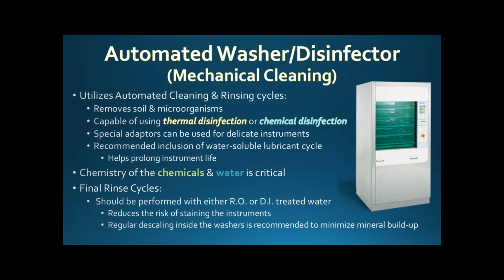Chemistry is so crucial. A quick story: at one facility I worked at in the past, we were having horrible staining of our instruments and problems with wet packs. When we boiled it all down, one root cause we found was our chemicals that we were putting in our washer, as well as the quality of our water, that was actually causing staining. It was putting mineral deposits onto our instruments, and we baked that all in when we put it in the sterilizer. It was also making it hold more moisture, more water. So it was causing a lot of different issues. If you're having issues in your final product, sometimes it really goes back to your washer disinfector.